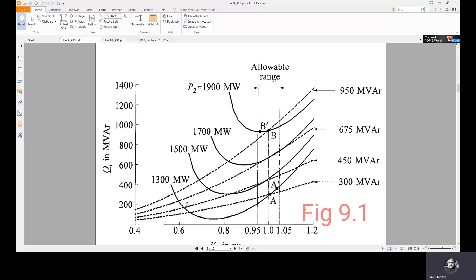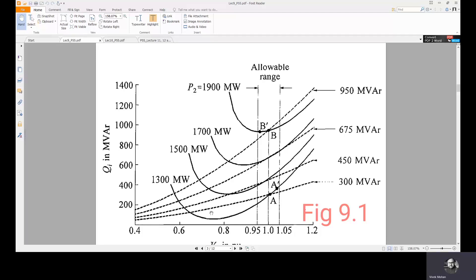The allowable operating range is always on the right side of the solid curves, not the left side, because on the left side the QV sensitivity is negative and those are considered unstable operating points. The capacitor's operating principle — injecting more reactive power when voltage is low — is valid only on the right side where positive QV sensitivity exists. This is why the right side defines the valid operating region.